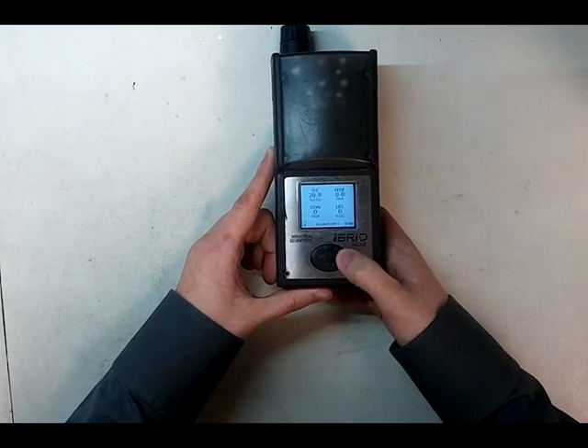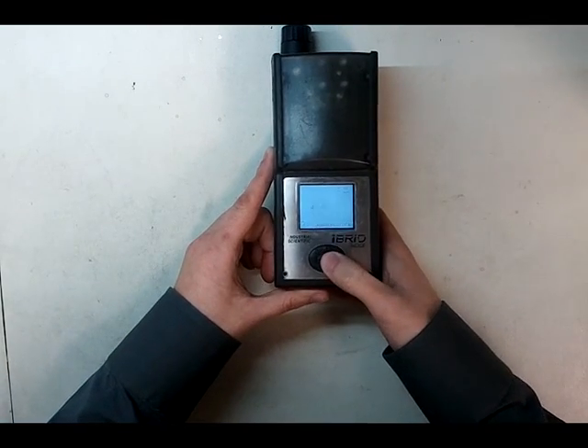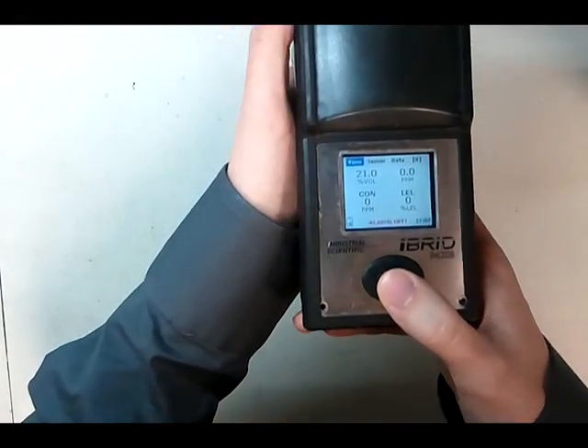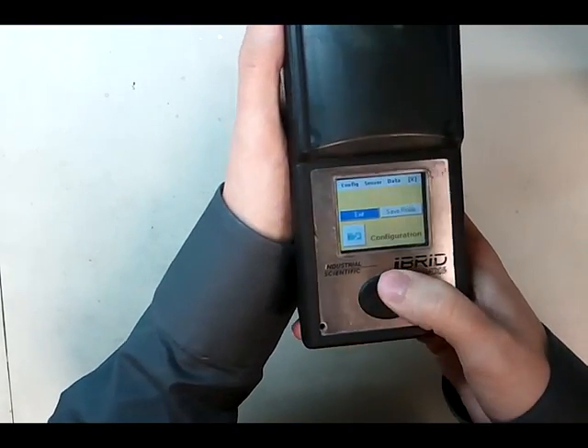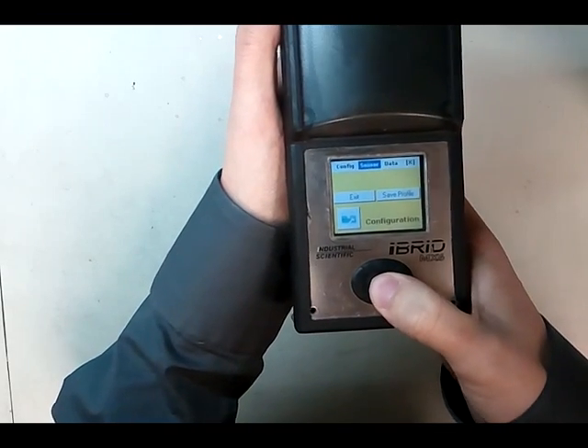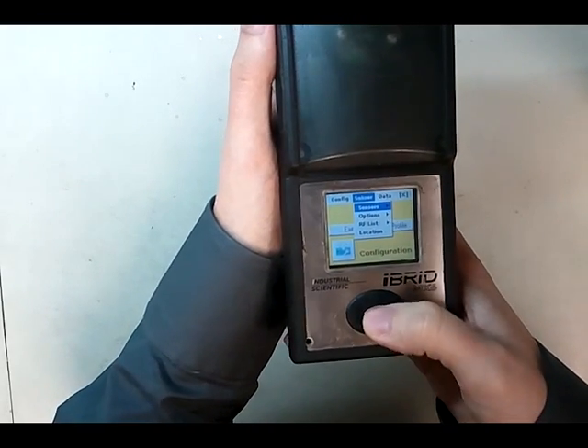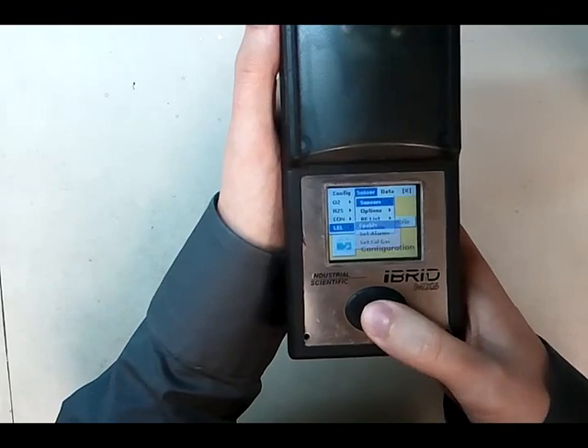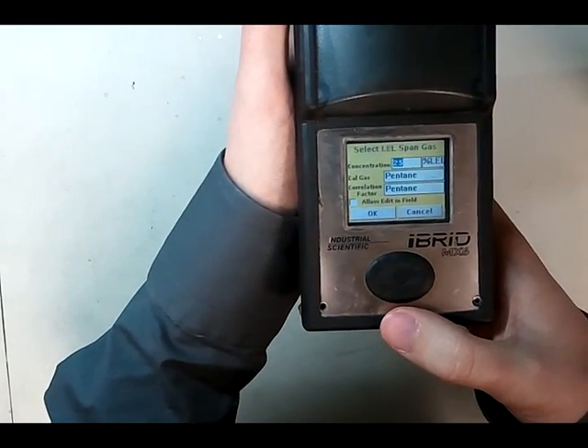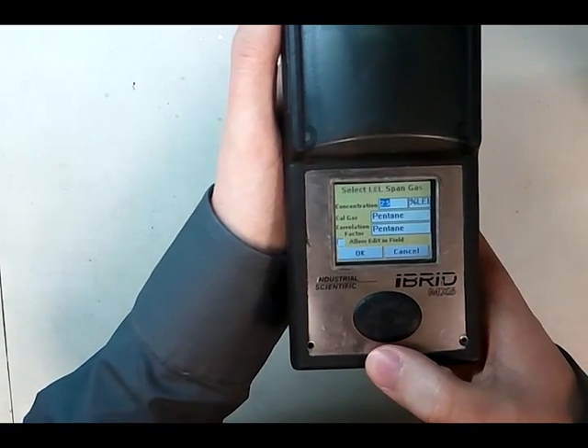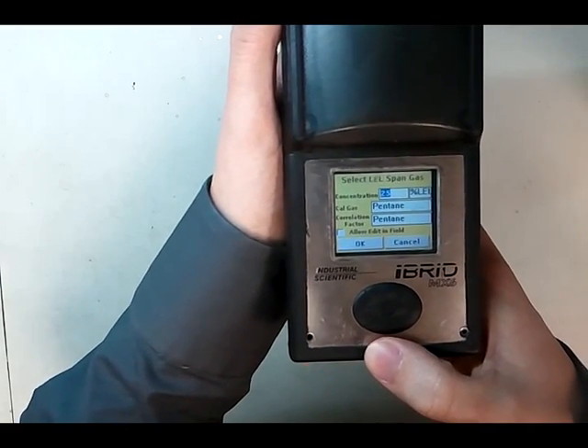First we're going to set up the monitor. It's currently set to be calibrated using pentane. I'll show you how we do that. Go to View, Configure, Sensor, Sensors list, down to LEL and Set Calgas. Right now you can see it's set to 25% LEL pentane, recommended by Industrial Scientific currently.